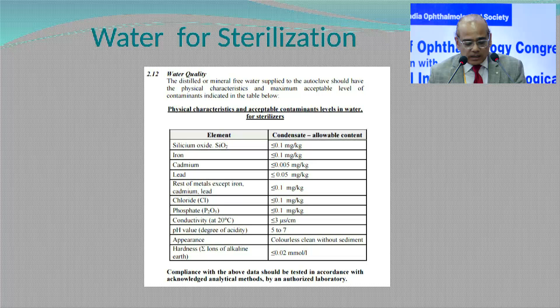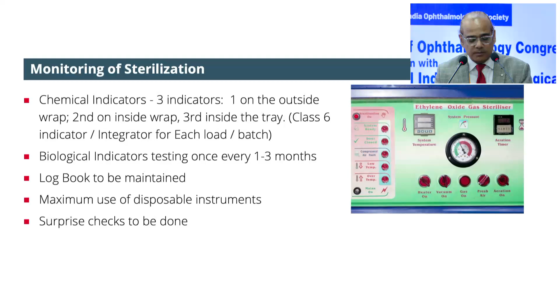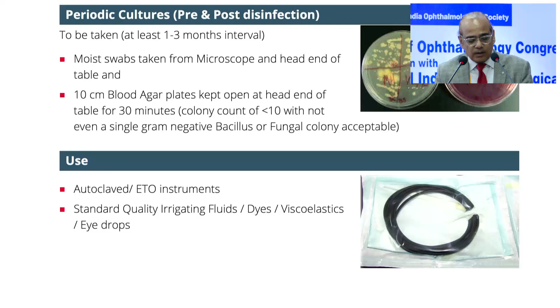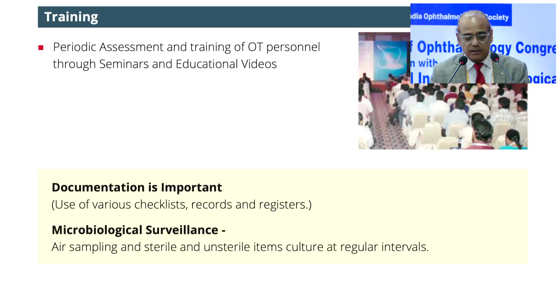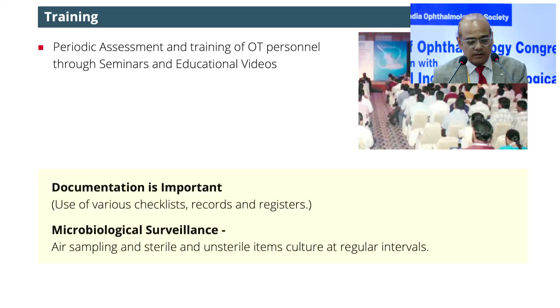Monitoring of sterilization is very important. There are 3 chemical indicators, and biological indicator testing needs to be done once every 1 to 3 months. A logbook needs to be maintained, with maximum use of disposable instruments, and there need to be surprise checks. Periodic cultures are needed, along with autoclaved or ETO instruments and standard quality irrigating fluids, dye and viscoelastics. Training is very important, so periodic assessment and training of OT personnel through seminars and educational videos. And of course, documentation is very important, along with microbiological surveillance.